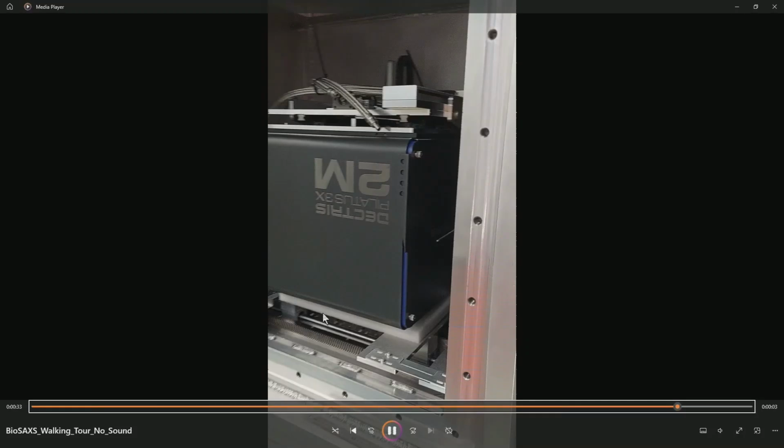The reason we've got that in that box is that once everything's closed up and it's under a vacuum, we can move that detector way up the front of the box. So if we're doing experiments where we know that the X-rays are going to scatter a lot, we can move the camera right up to the box, close to the sample. But if we're doing experiments where we don't expect lots of deviation, we move the camera way up the back of the box, and that means we can detect a very small deviation over that 8 metres. A very small deviation will turn into a larger deviation, and we can measure it.